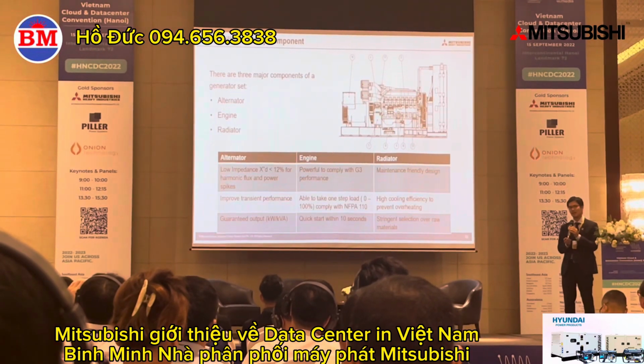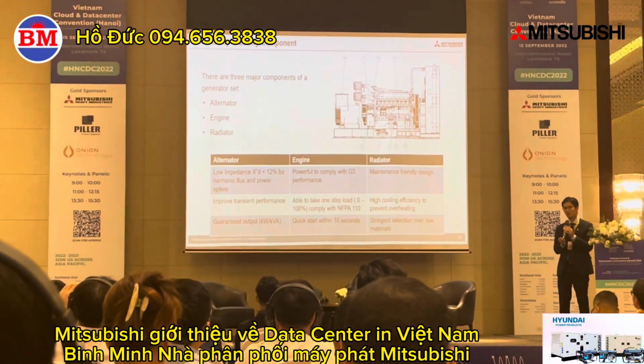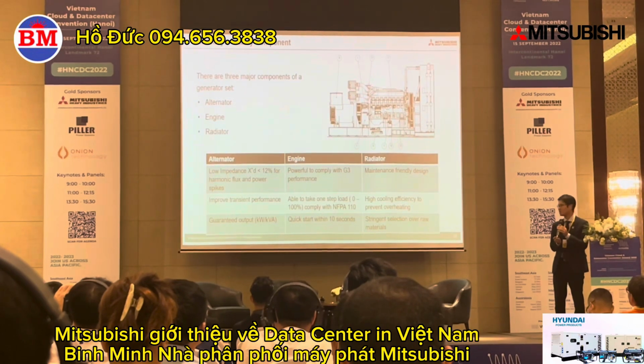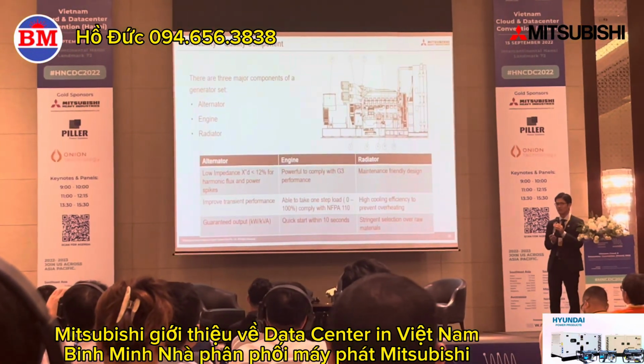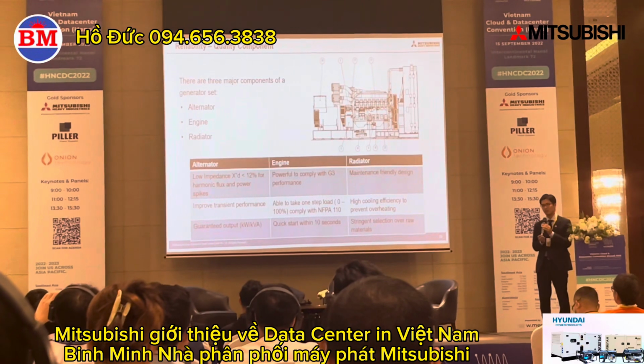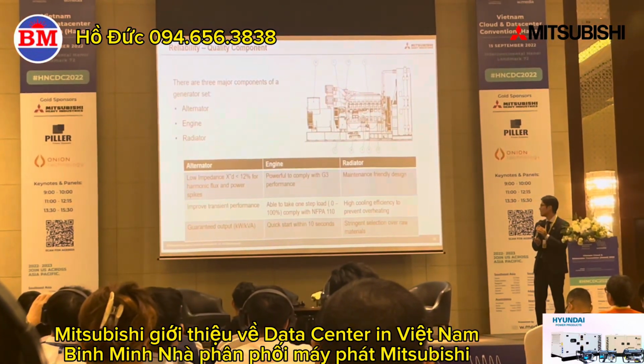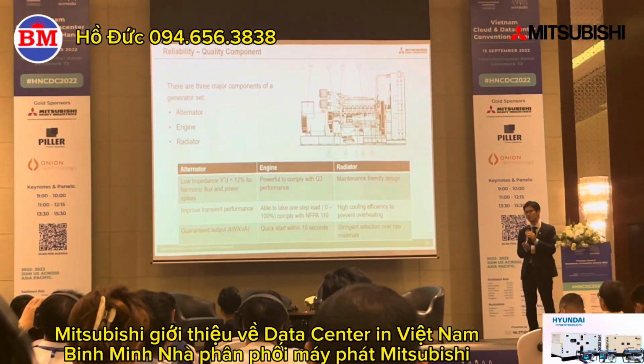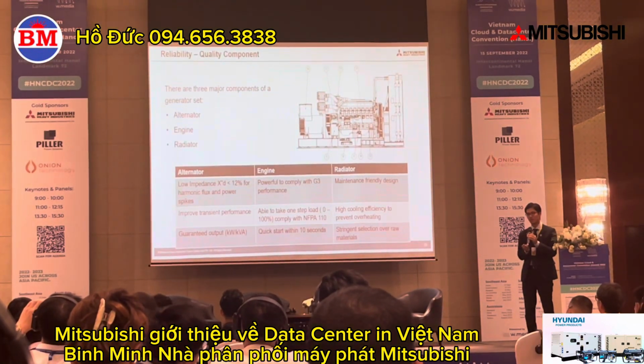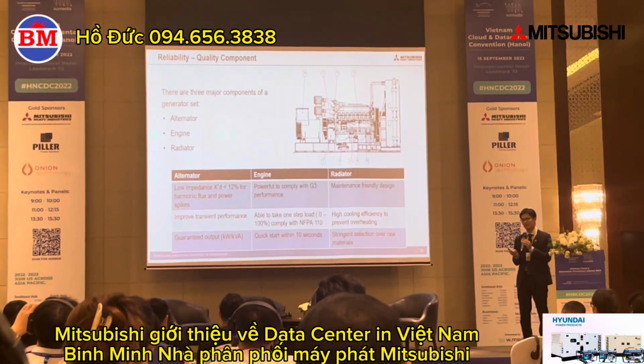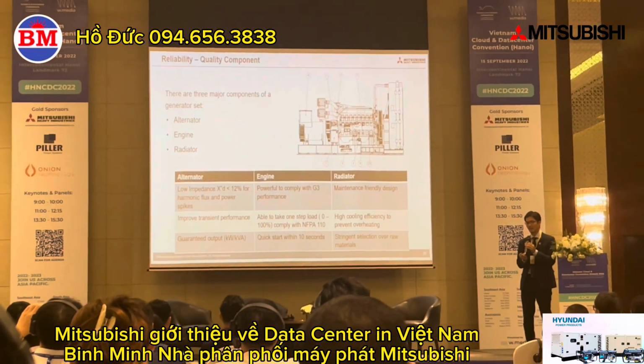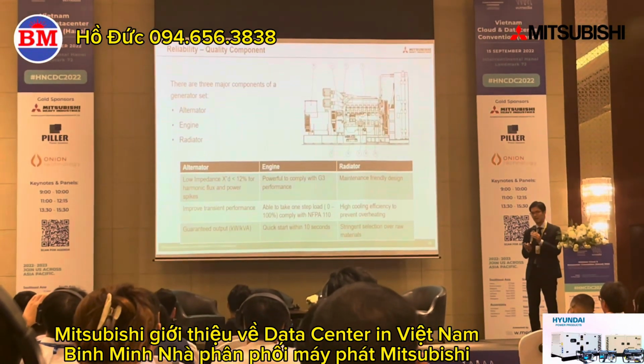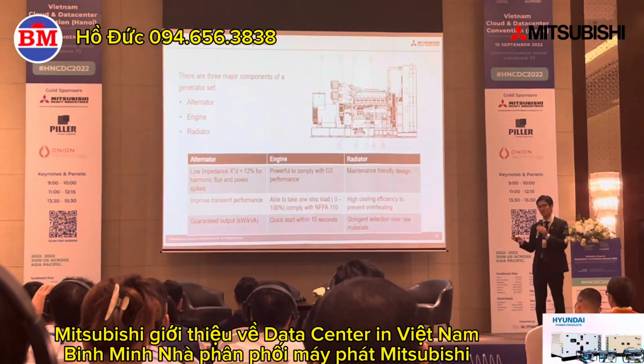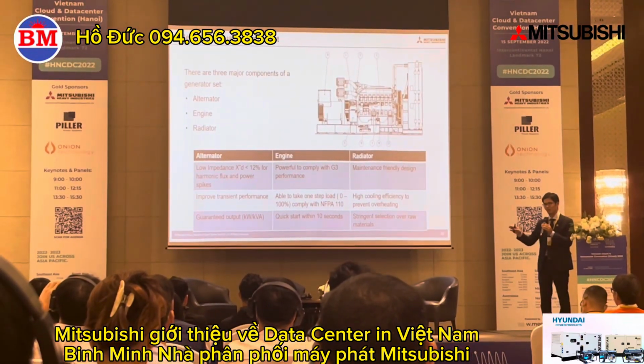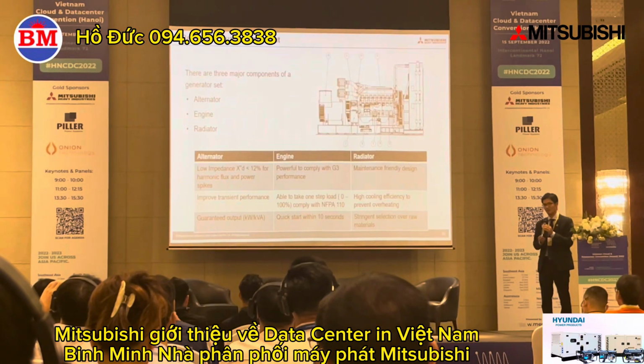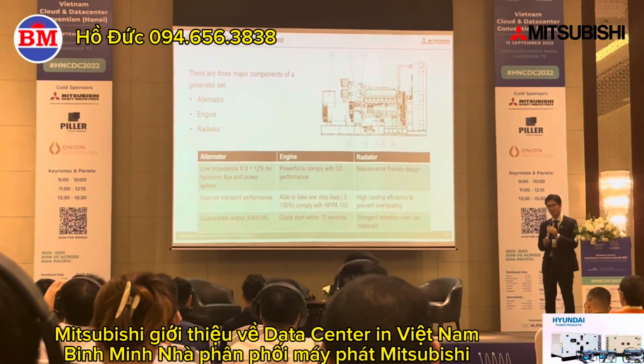The radiator itself is important to prevent overheating in worst-case conditions, so designing the criteria for the radiator is very important. We had a customer who said our radiator was over capacity because he tested it at site, and according to his experience, our cooling water temperature was much lower than competitors. This is one example of our criteria setting.